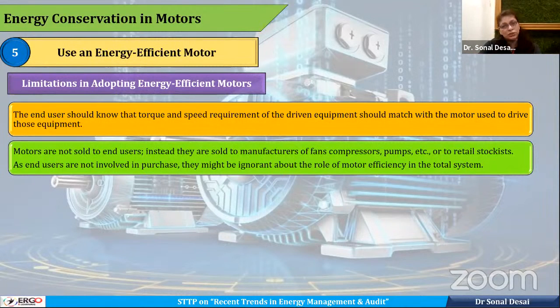So if I want to make my fan to be sold at a lower rate, obviously I'll select a motor which has a lower initial cost. So a manufacturer of a fan, motor, pump, or any other equipment who is using the motor will not always go with the high energy efficient motor. This comes into the picture when they have to give a star rating and the labeling program has to be followed. When they have to put a star rating or when they have to meet certain mandates, in that case, they will go with the motors which are super efficient. Otherwise, they will just select based on the criteria or based on the warranty and guarantee terms.